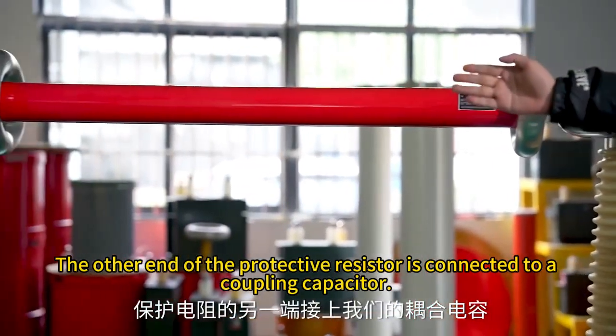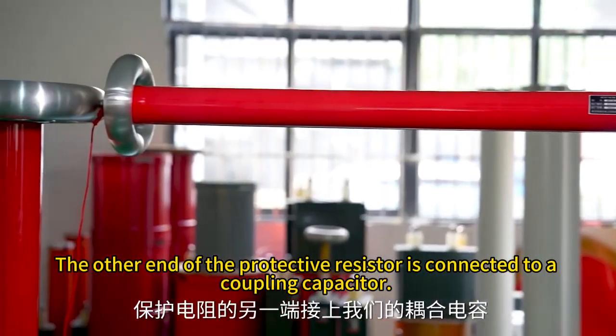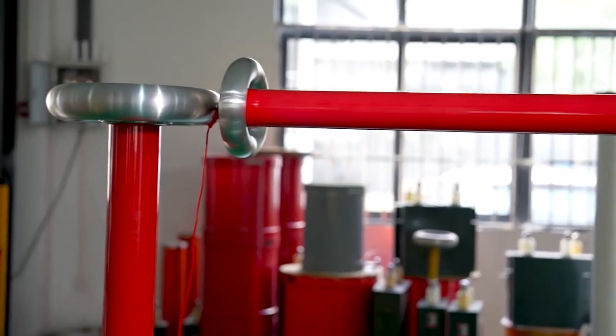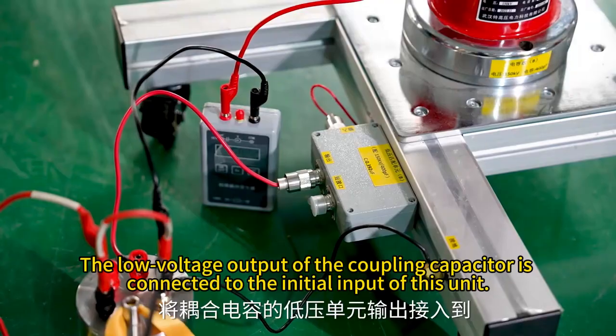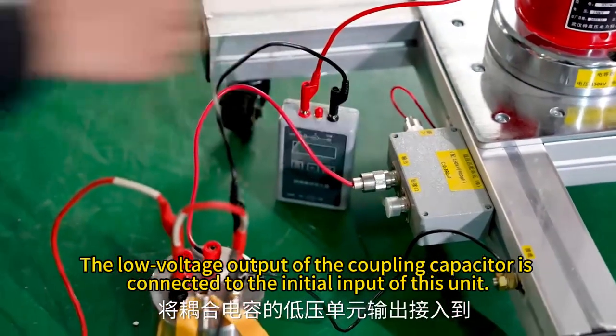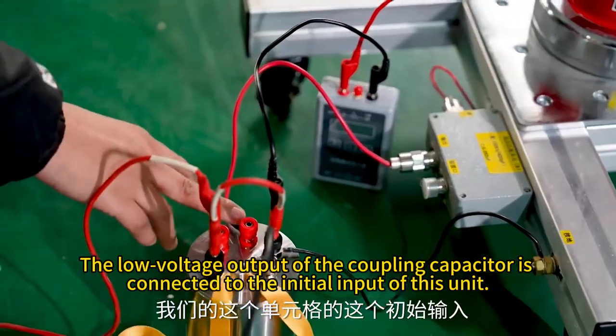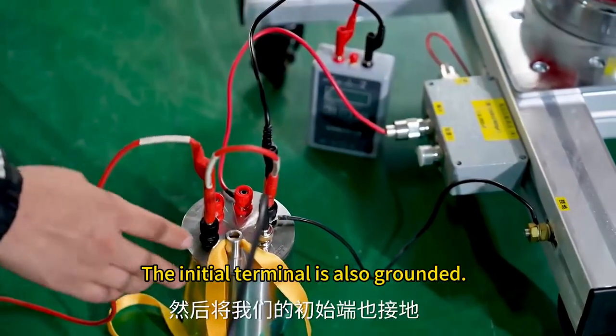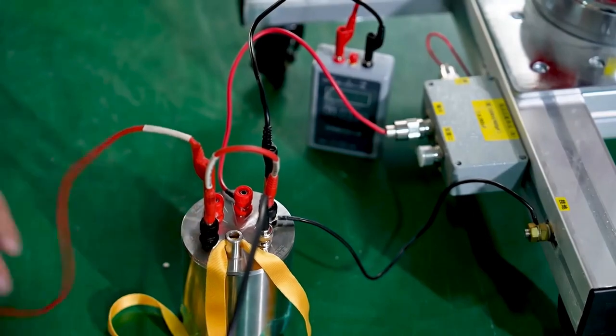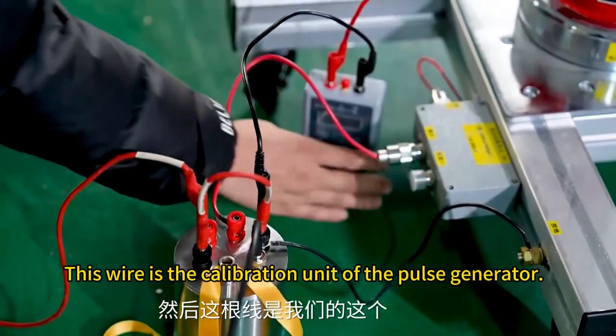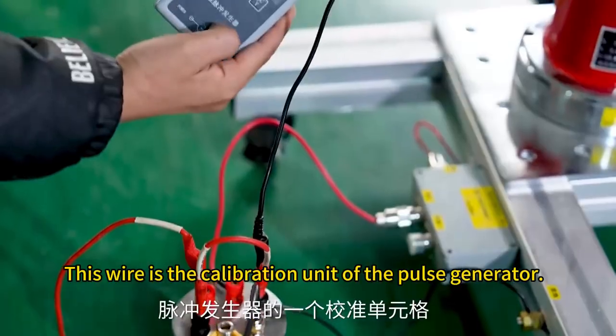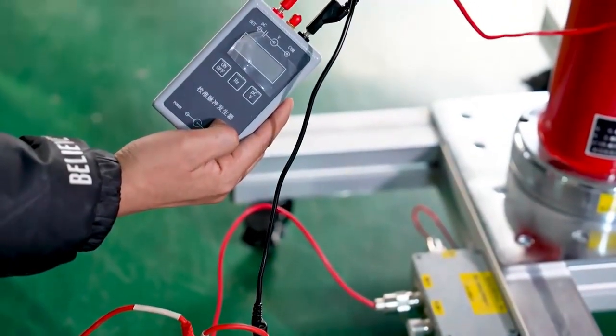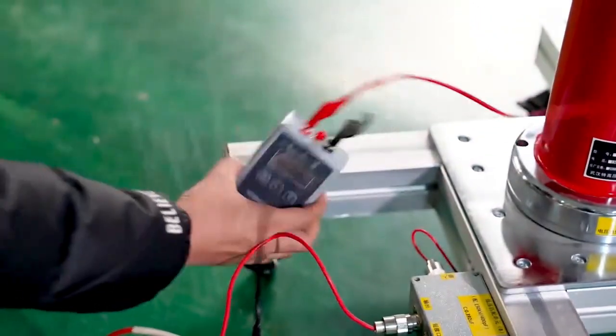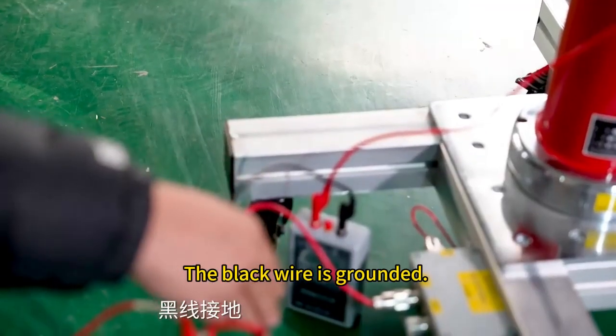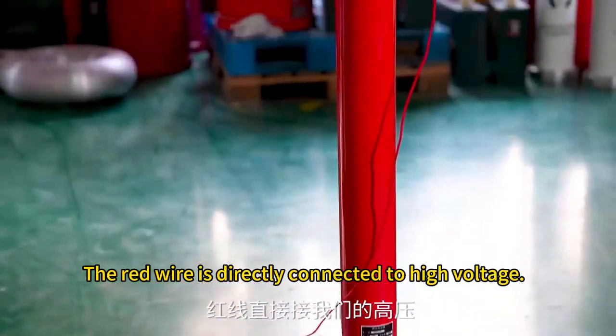The top of the test transformer is connected to a protective resistor. The other end of the protective resistor is connected to a coupling capacitor. The low voltage output of the coupling capacitor is connected to the initial input of this unit. Then, the ground is connected to ground. The initial terminal is also grounded. This wire is the calibration unit of the pulse generator. The black wire is grounded. The red wire is directly connected to high voltage.